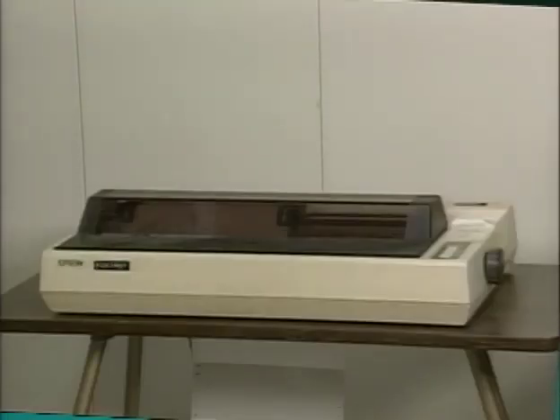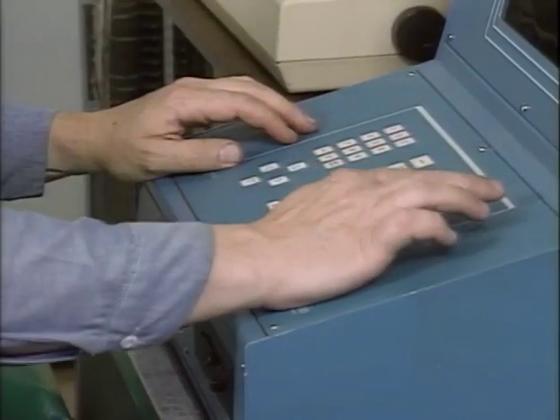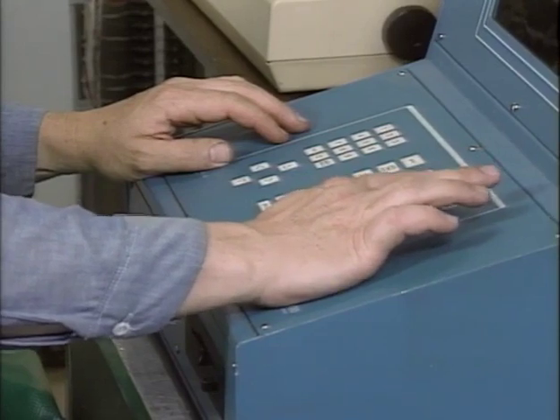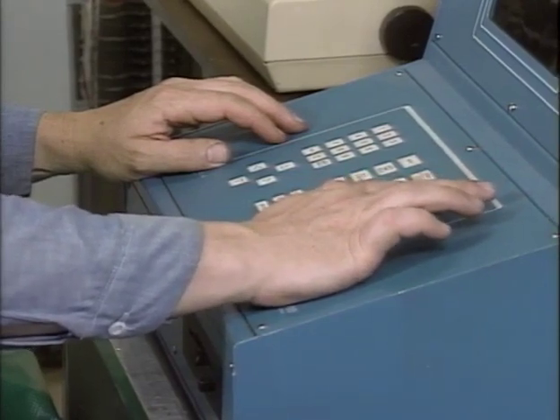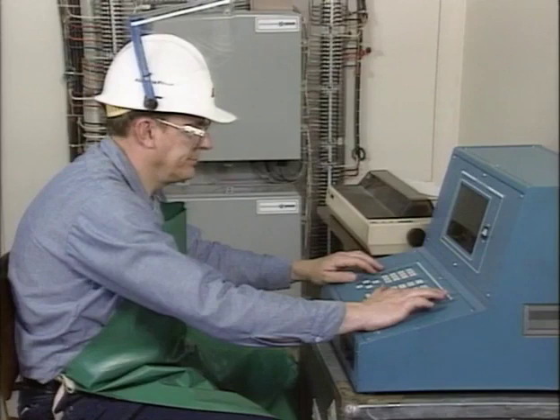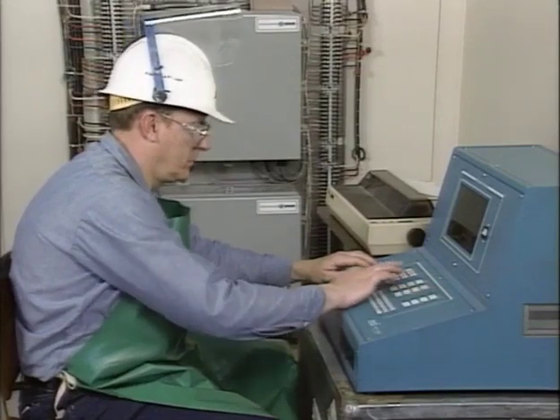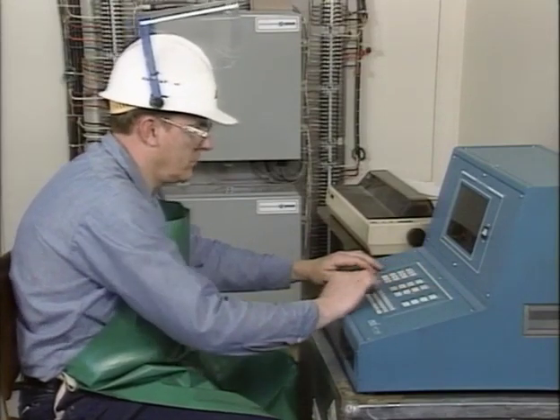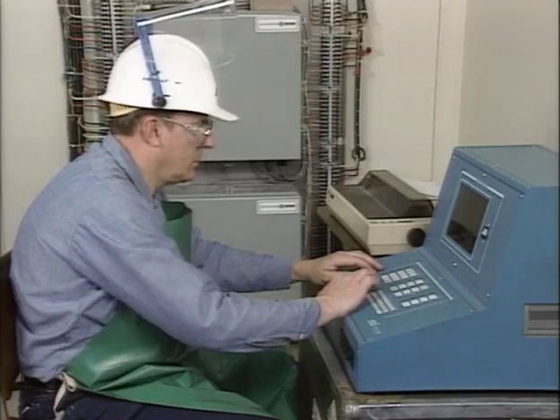In addition, a printer may be connected to the control unit to provide printouts of cell and battery voltages. If a printer is used, the control unit is programmed to provide a printout at specific times during the test. After the control unit is programmed, the time and date are entered and the tests are started.